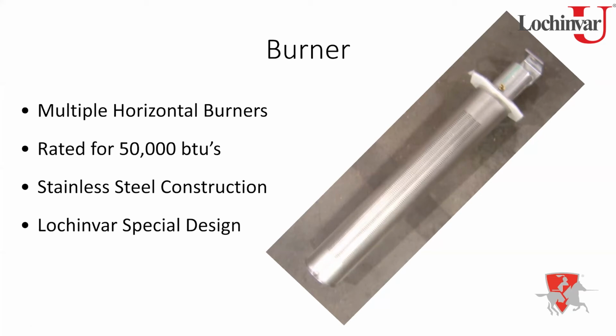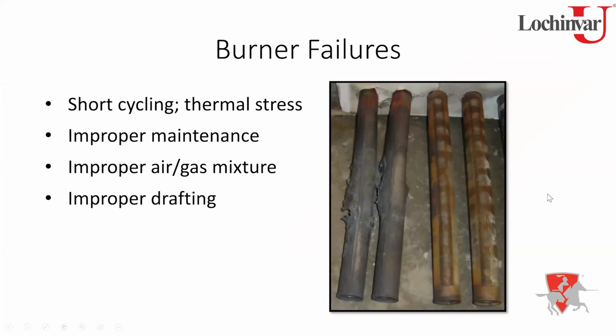Now, the burner that you see here in this picture, you'll also notice up here at the top there's kind of a little brass fitting. You'll have one burner in the bunch that will have that fitting, and that is for our air hose to connect to from our air pressure switch. We'll talk a little bit more about that in a second as far as what the air pressures are that we're looking for. Now, as far as damage to the burners, what causes damage? Primarily, you've got two things that will cause damage: either thermal stressing, which will crack the burners, or the burners just get too hot, they overheat. Now, your thermal stress is generally due to short cycling, right? You're basically starting and stopping too rapidly. That metal's expanding and contracting. So that burner's going to sit there and basically move.